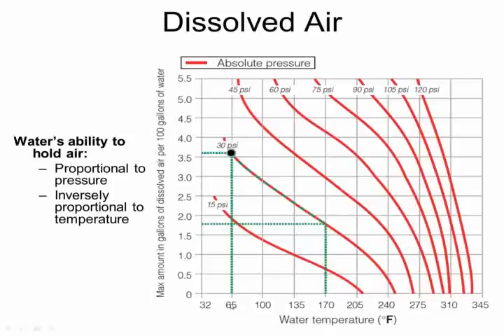Now, nothing's happened. You haven't fired the boiler on yet. All the air is out of the system, and you're just getting ready to fire the boiler on for the first time. So we're at basically room temperature, 65 degrees, 30 psi. At that point, before anything happens, that water sitting in that boiler has 3.6 gallons of air for every 100 gallons. A lot of air.